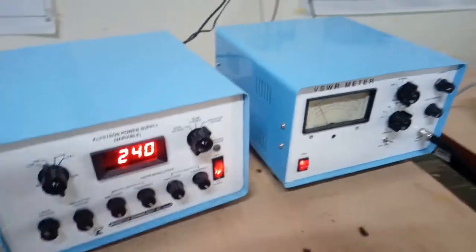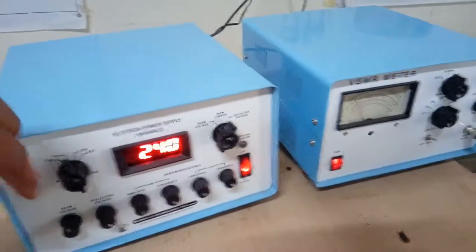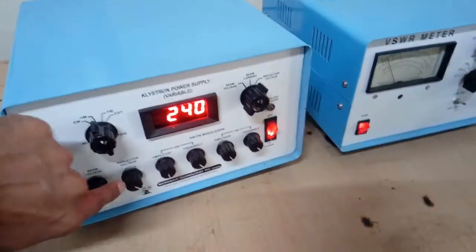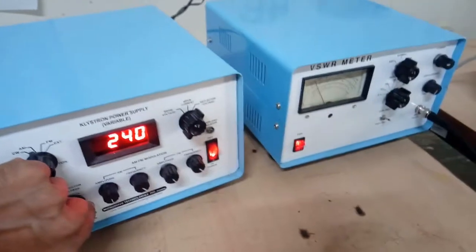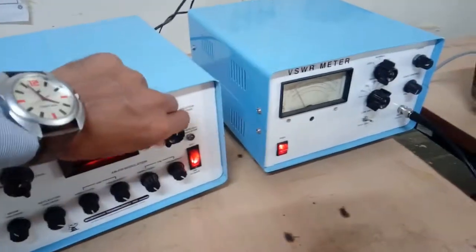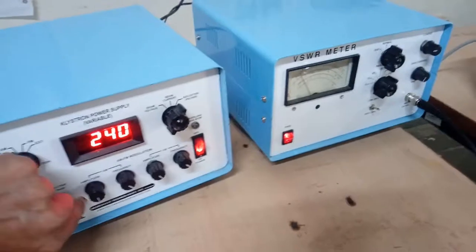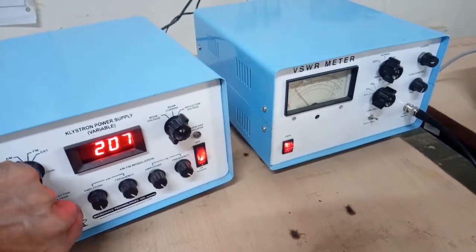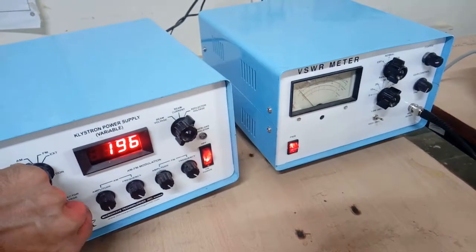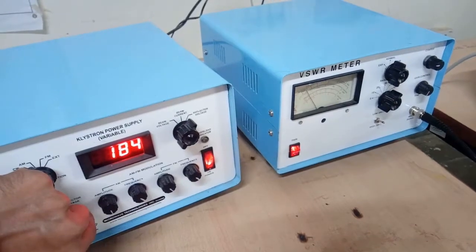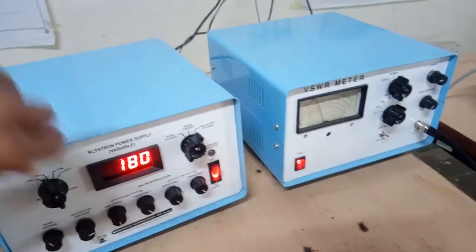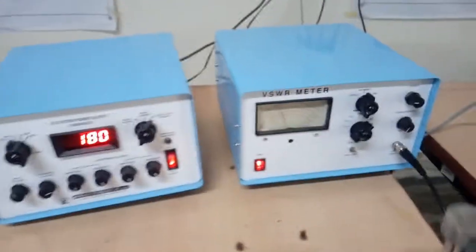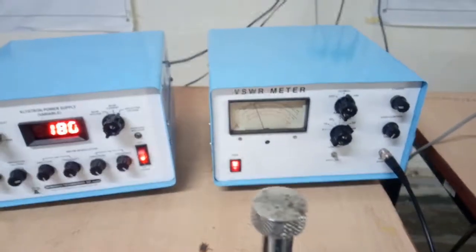Now we will change the reflector voltage. Reflector voltage is fully clockwise, we have to reduce it now in anticlockwise direction. So when it is increasing, we will keep it at 180. You can see the deflection in VSWR meter.